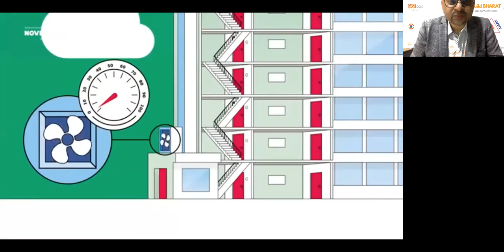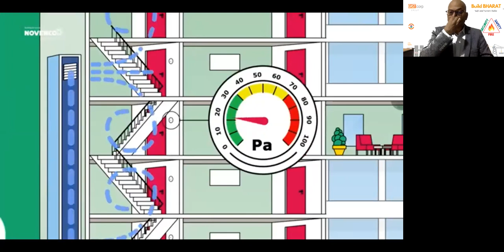This is coming from one of the OEMs, but it very beautifully explains the concept of pressurization. There is no audio here, just a video. So there is a fire, there's a fire alarm which is ringing the bell. You have a staircase, you have a supply fan, which is part of your pressurization system. You are starting to build the pressure into the staircase lobby. It started creating the differential pressure I explained to you. We are expecting 50 Pascal in the staircase by local law. So that's how we are building the differential pressure between the staircase and the lobby, so that the smoke will not enter. People have started evacuation.